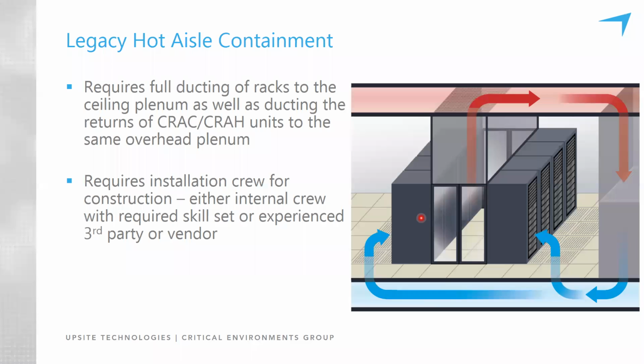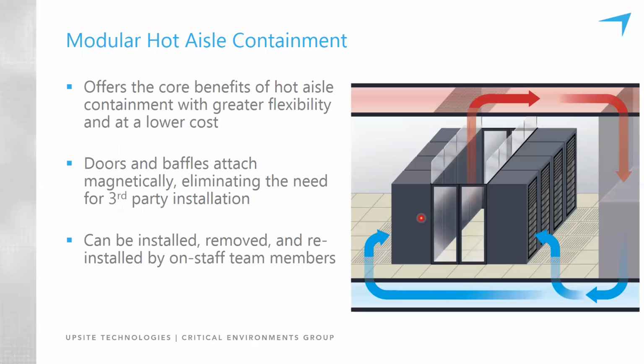When we look at the modular version of hot aisle containment, we don't have a full duct, a full chimney to the ceiling plenum, but the benefits can be very close to the same. The amount of air being delivered to the IT equipment is crucial in the process of optimization. That is, balancing the amount of conditioned air flowing through all the cooling units as closely as possible to the amount of air flowing through the IT equipment.